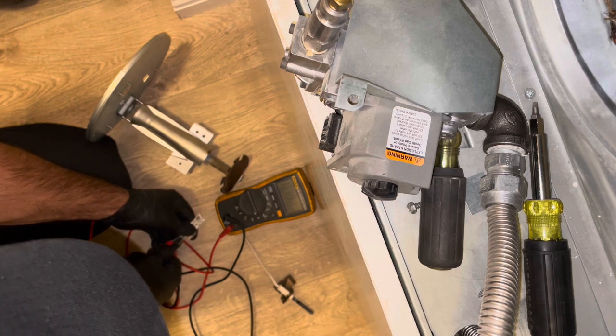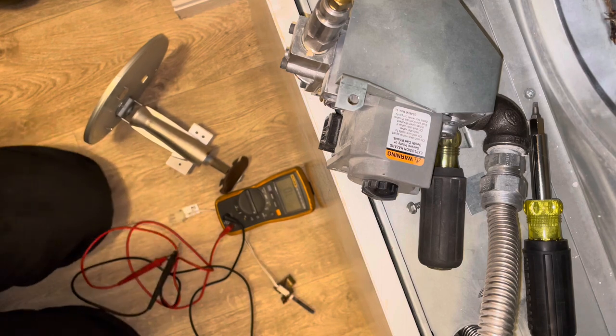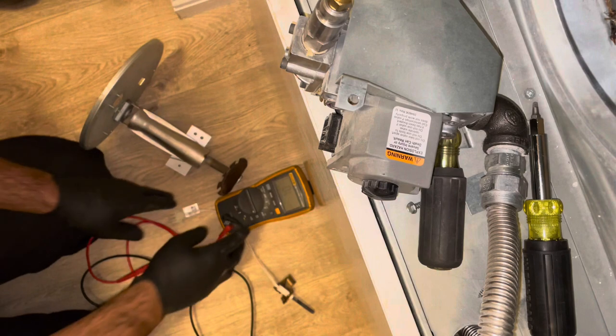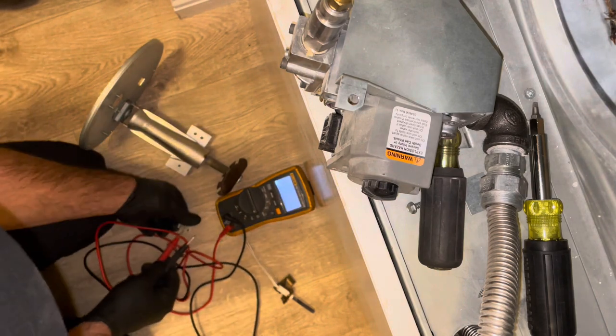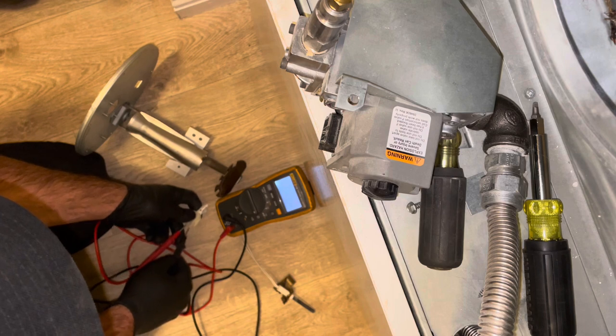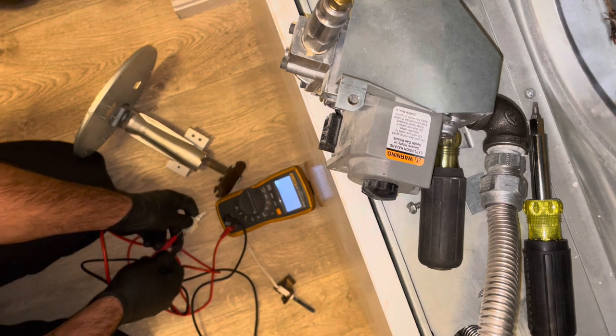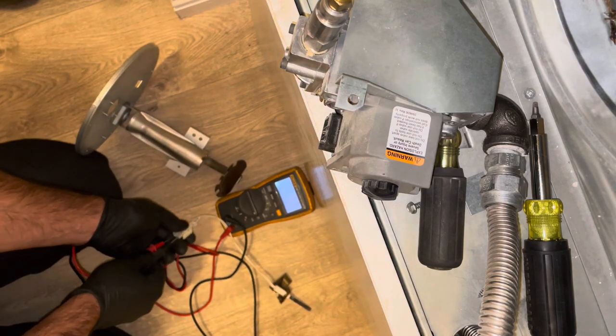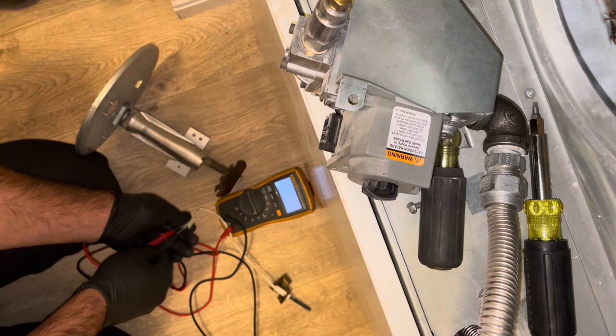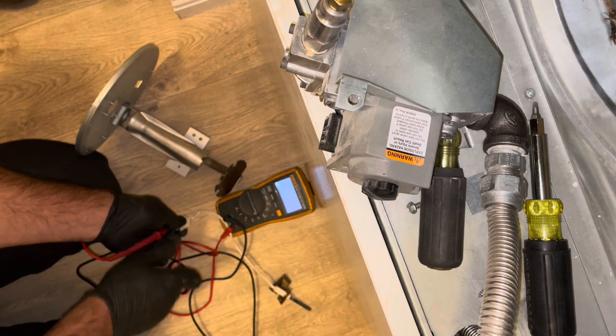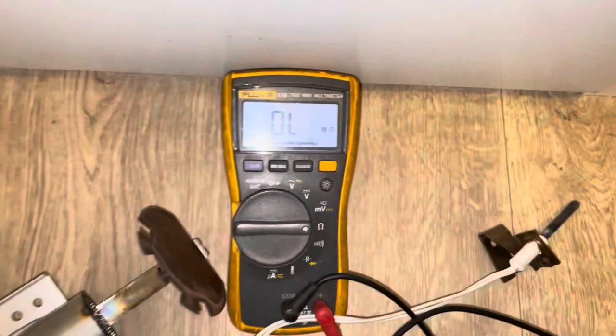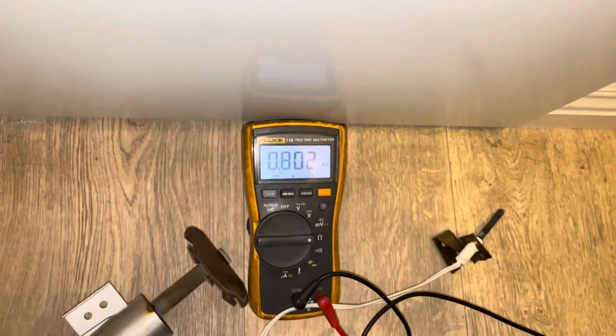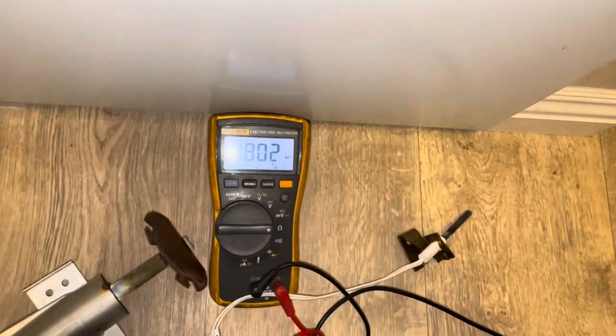Yeah, it's weird. All right, let's get a new... let's see if you guys can see this. So we're ohming it out. I don't know if you can see that. Maybe a little bit. It's just got some weird resistance. So let's go get a new igniter.